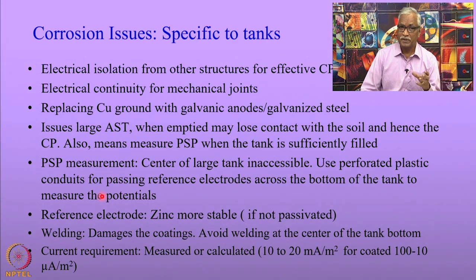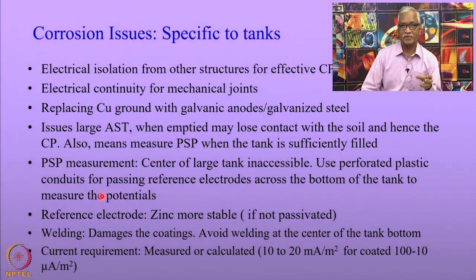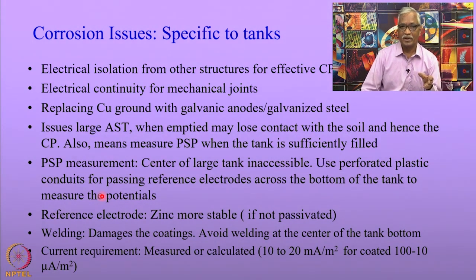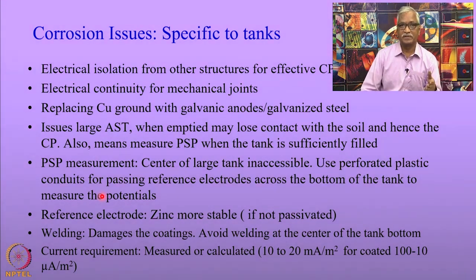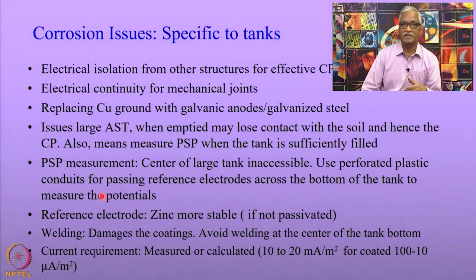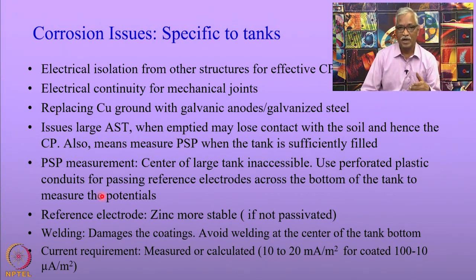It is also possible to use zinc electrodes, since zinc electrodes are just buried in the soil. Normal reference electrodes like copper-copper sulfate or silver-silver chloride have solutions that dry up over time, so these electrodes become damaged and do not show reliable values.